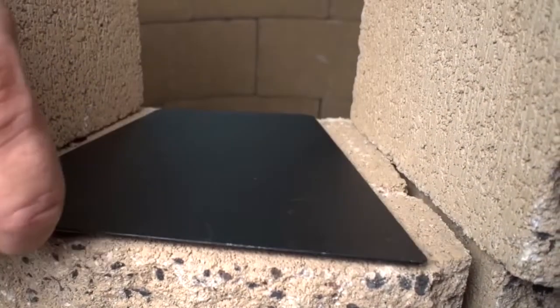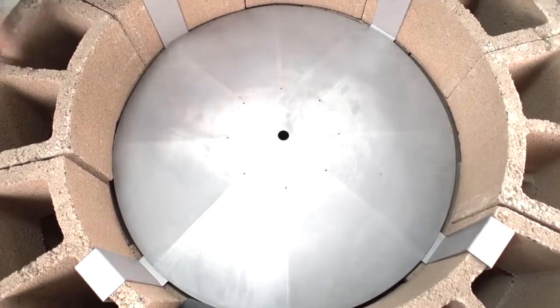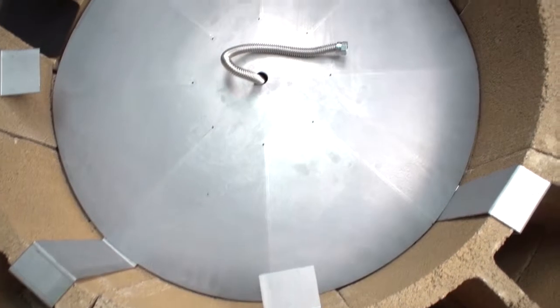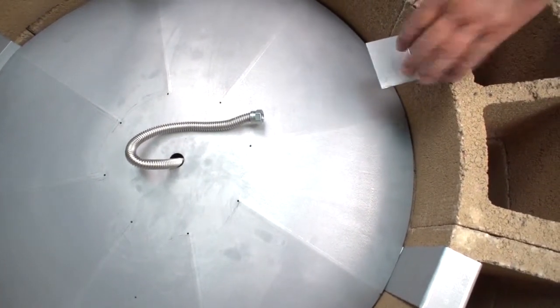Place the block cover over the open block. Place the heat shield on the retaining brackets in the center of the fire ring. The supply line will need to run vertically through the heat shield in the center of the fire ring, up to where you will connect it to the gas regulator using a half-inch flared flex line. There is a one-inch hole in the heat shield for the gas line.